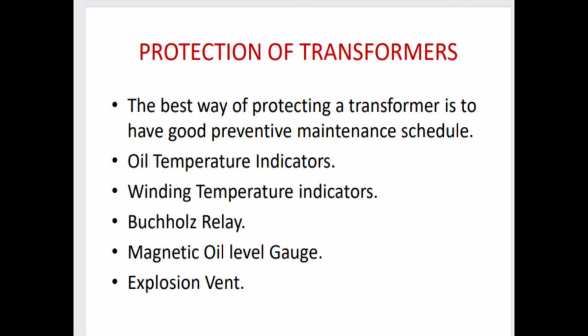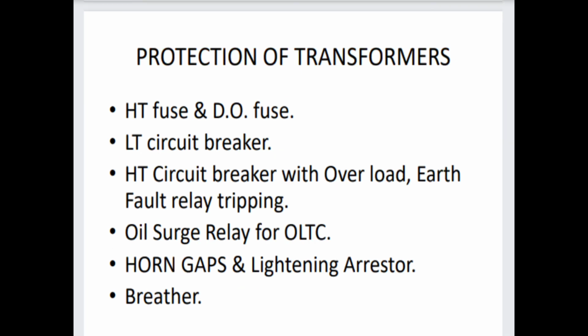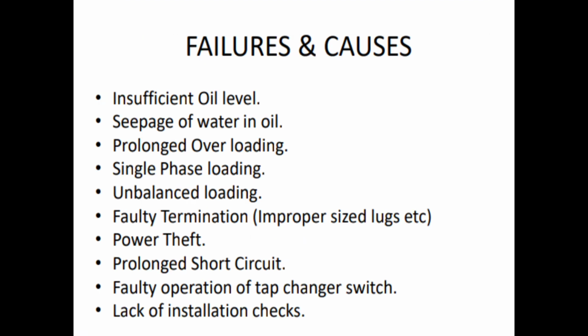So, protection of transformer. The best way of protecting a transformer is to have a good preventive maintenance schedule, oil temperature indicators, winding temperature indicators, Buchholz relay, and magnetic oil level gauge and explosion vent. So, these are the protection of transformer. Then, protection of transformer next are HT fuse and DO fuse, LT circuit breaker, HT circuit breaker with overload earth fault relay tripping, oil surge relay for OLTC, horn gaps and lightning arrestor and breather. Failure and causes of transformer. First is insufficient oil level, second is seepage of water in oil, third is prolonged overloading, fourth is single phase loading, fifth is unbalanced loading, sixth is faulty termination, seventh is power theft, eighth is prolonged short circuit, ninth is faulty operation of tap changer switch, 10th is lack of installation checks. So these are the failures and causes.